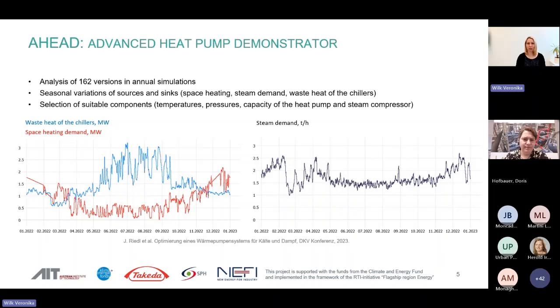And another important question was the temperature in between these 2 heat pump systems. So how high should the temperature be that the steam generating heat pump is producing, and where should the steam compressor then take over? And to solve this question, we have carried out a large number of annual simulations, basically simulating 162 versions of this system to come up with the best suitable compromise between investment and operation costs to yield as much steam as possible, also considering economic boundary conditions.